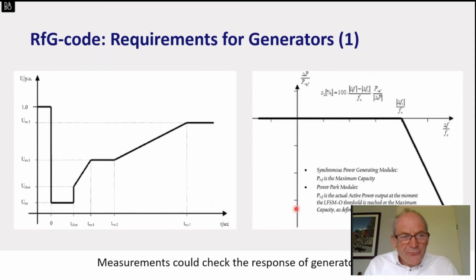For this reason, we have introduced RfG codes, the requirements for generators. These requirements take over some of the task of the big generators: solar systems and wind parks should also be able to respond to deviations in frequency or voltage. So when the frequency is going up, which means there is overproduction, there should be a reduction in production. And the other way around, when the frequency is going down, the production should be increased, or otherwise the load should be decreased.